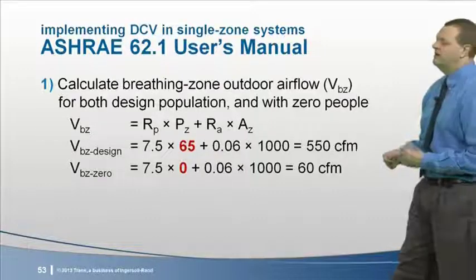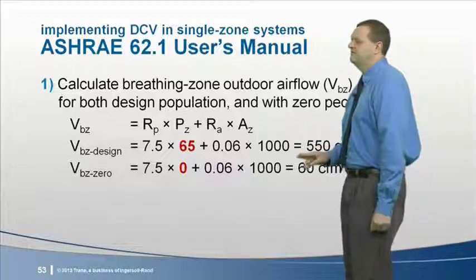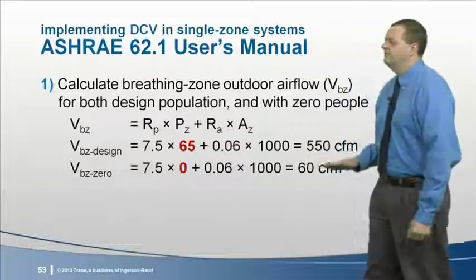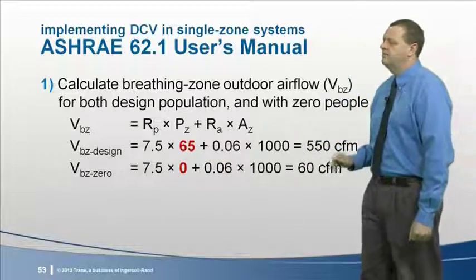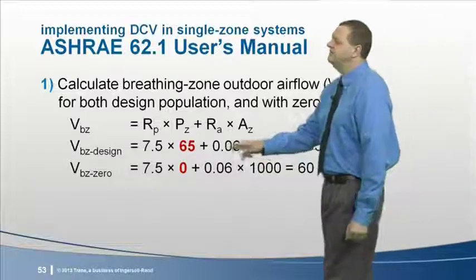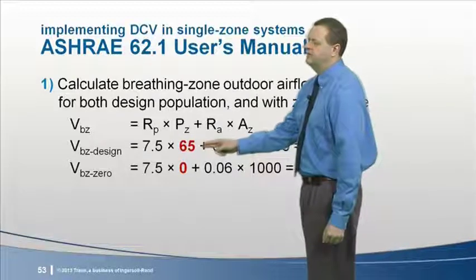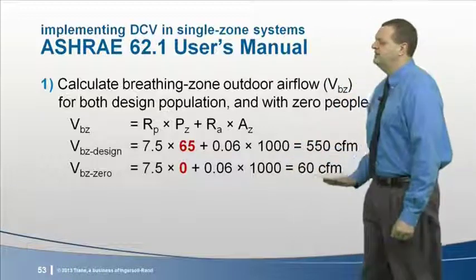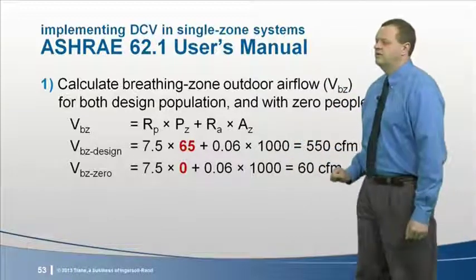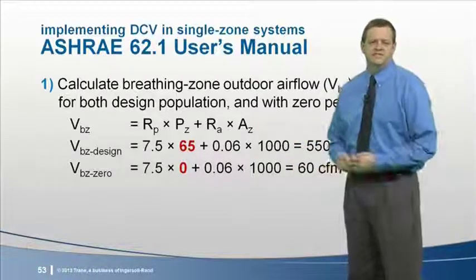Using the rates required by ASHRAE 62 for this type of space, our example classroom needs 550 CFM of outdoor air when all 65 people are present. But it only needs 60 CFM when the zone is unoccupied, but the ventilation system is still operating.